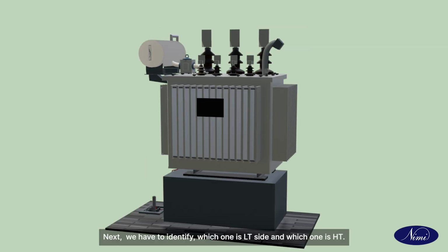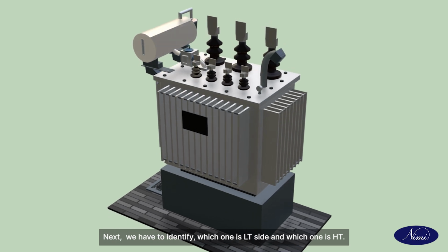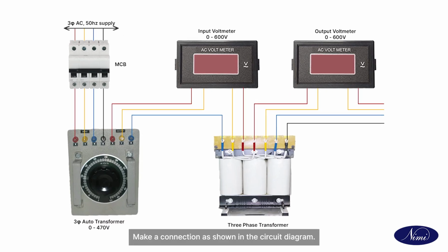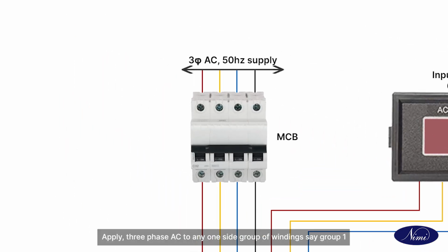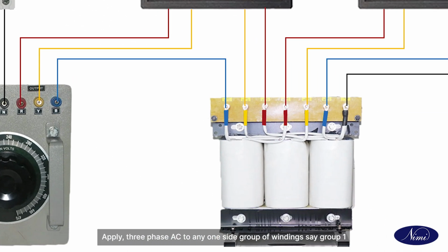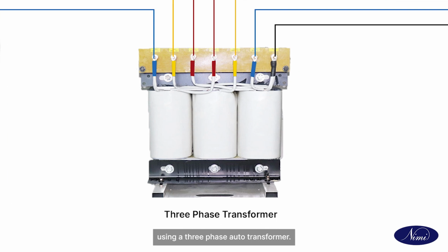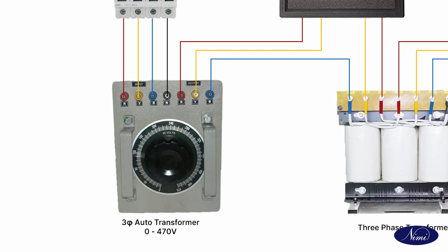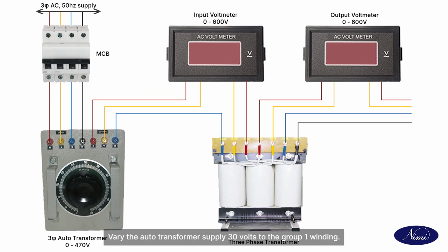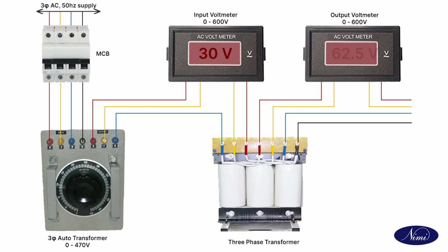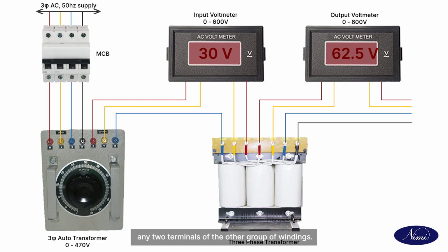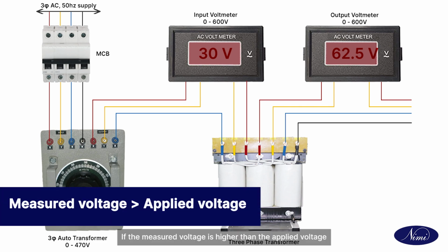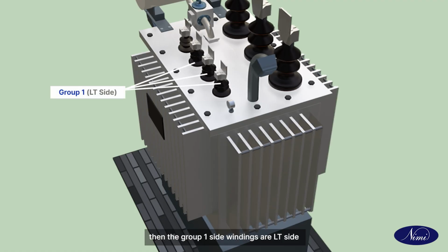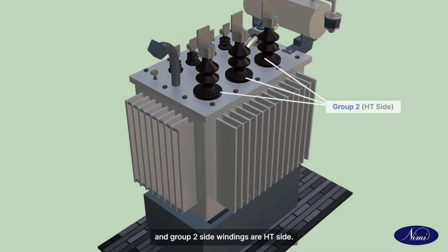Next, we have to identify which one is LT side and which one is HT. Make a connection as shown in the circuit diagram. Apply 3-phase AC to any one side group of winding, say group 1, using a 3-phase auto transformer. Vary the auto transformer supply to 30 volts to the group 1 winding. Measure the voltage between any 2 terminals of the other group of windings. If the measured voltage is higher than the applied voltage, then the group 1 side windings are LT side and the group 2 side windings are HT side.